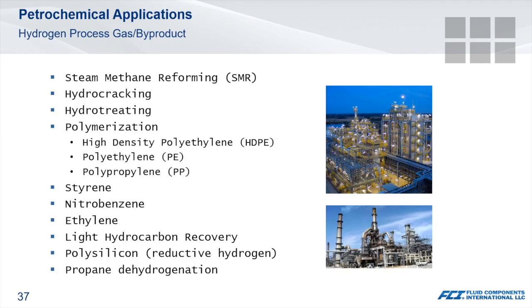There are numerous applications in the petrochem industry that have been around for quite some time, which either consume or produce hydrogen. Depending upon the process, the parameters can vary greatly. Line sizes ranging from 1 inch to 10 inch. Flow rates can be as low as 0.1 pounds per hour and as high as 10,000 pounds per hour. Process pressures in the range of 100 to 1,000 psig. Temperatures from 60 to 200 degrees Fahrenheit.